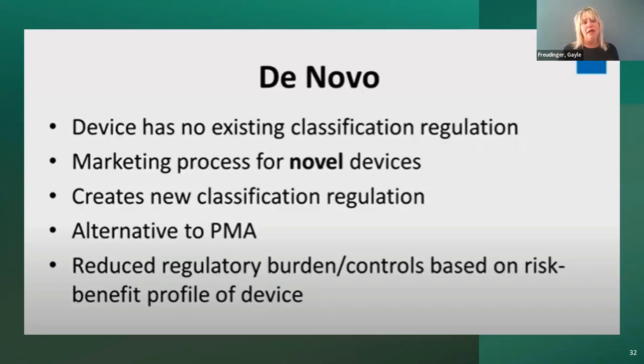The de novo submission is for when a device has no existing classification regulation, and general and special controls can apply here. You want to provide reasonable assurance of safety and effectiveness for the intended use, but for which there's no legally marketed predicate device. So, for example, you might have a diagnostic test that can be used for multiple indications, and there's really nothing exactly like that out there. That's where you might want to do a de novo request. Deciding whether to go the de novo route or emergency use authorization or one of those routes is really important for how much time it's going to take to develop the device and how much testing needs to be done. So you really want to work with an expert, run your ideas by them, see what questions you might have for the FDA, and make sure you're on the right path.